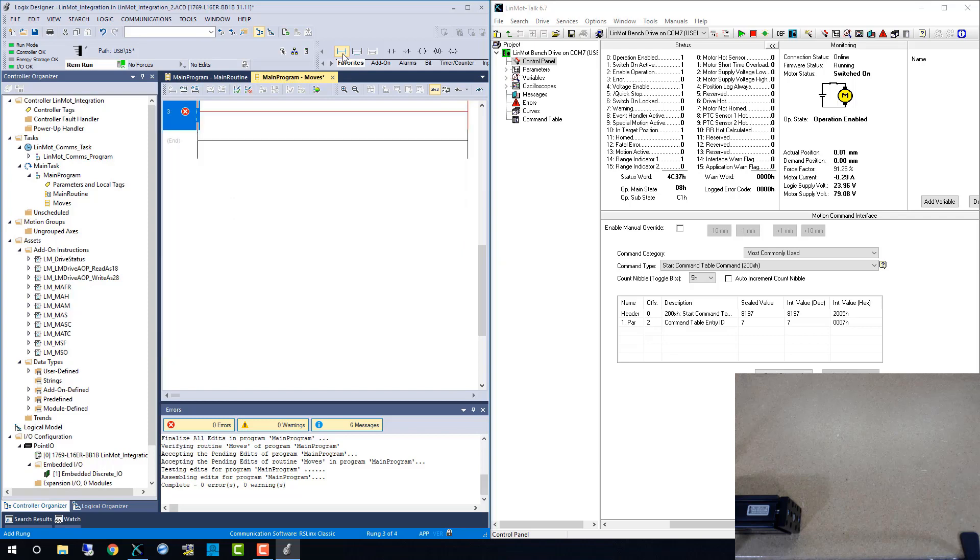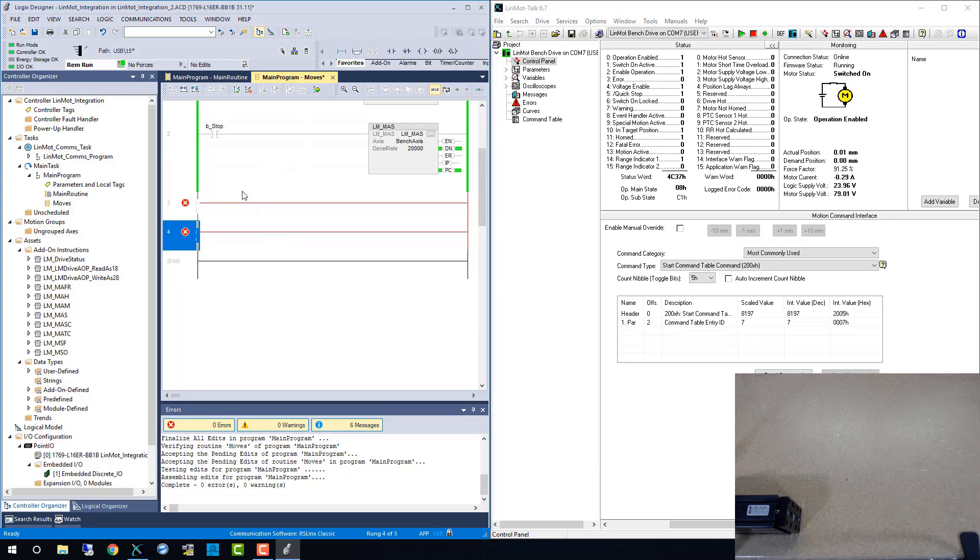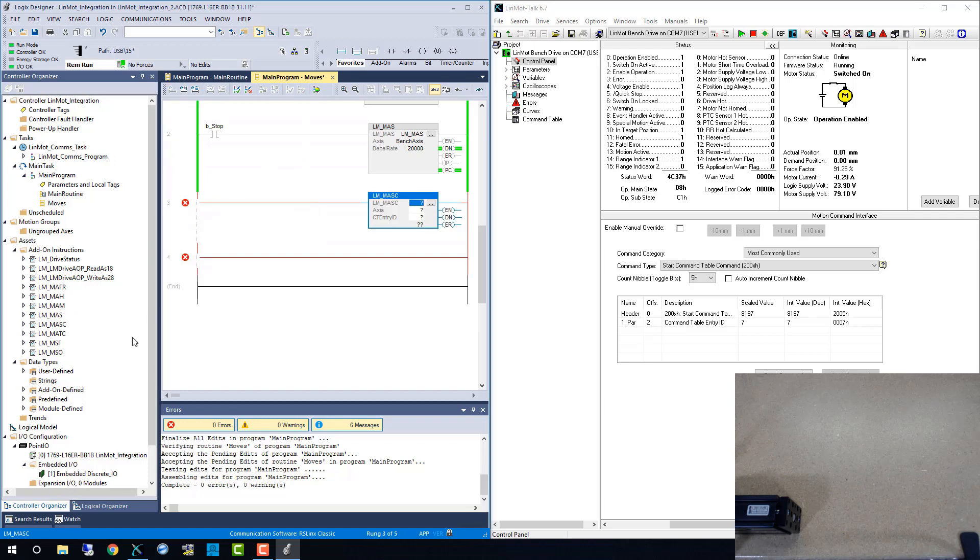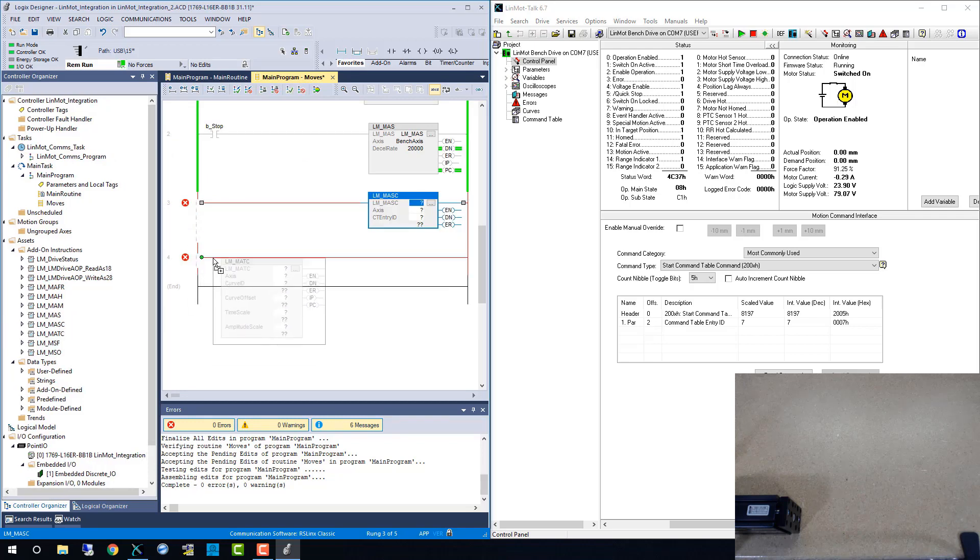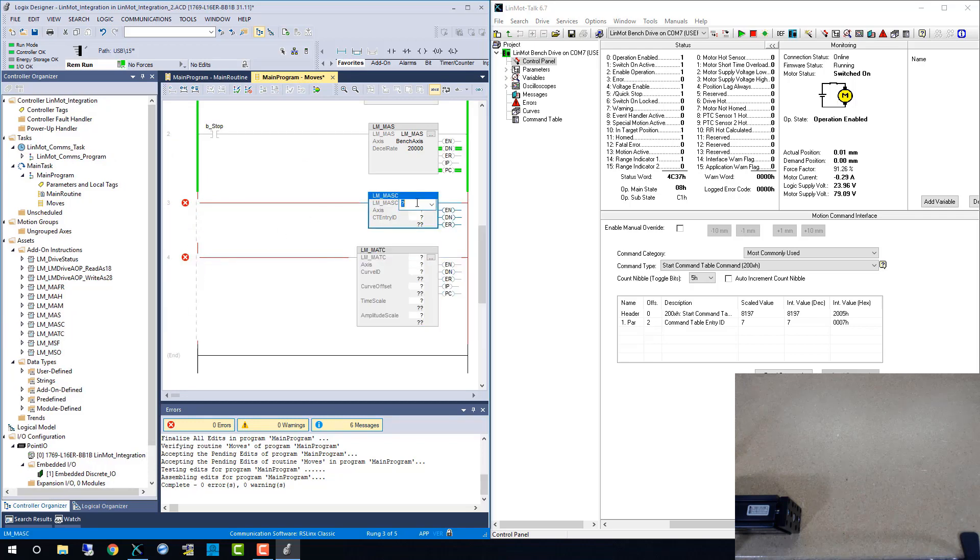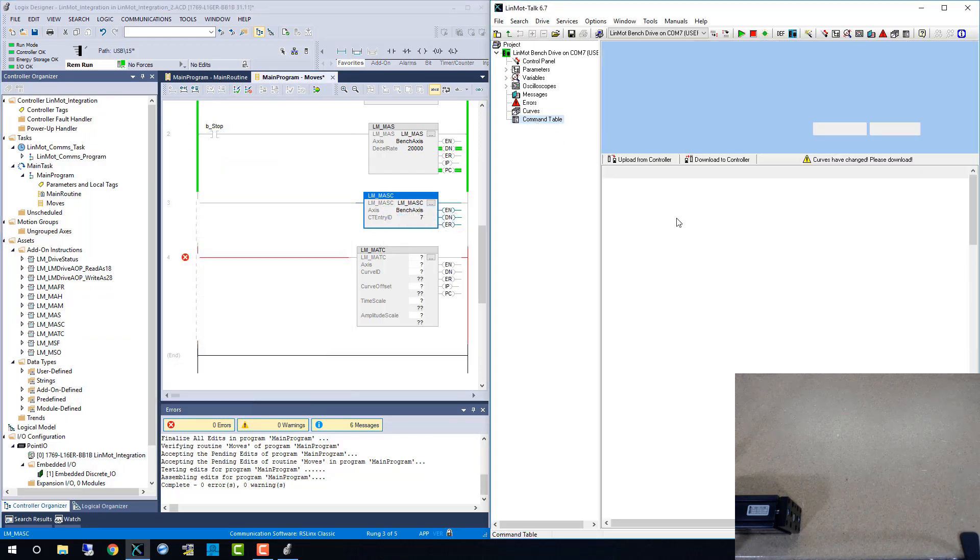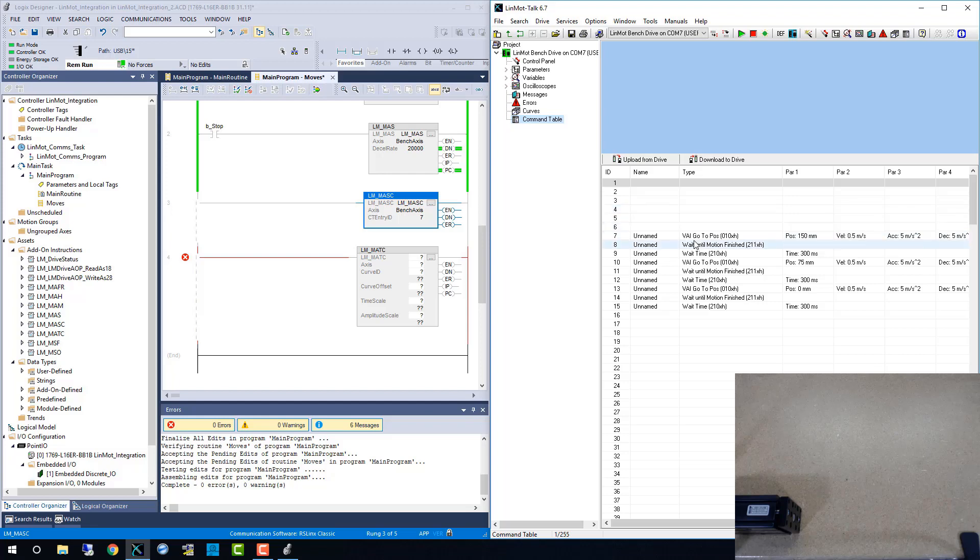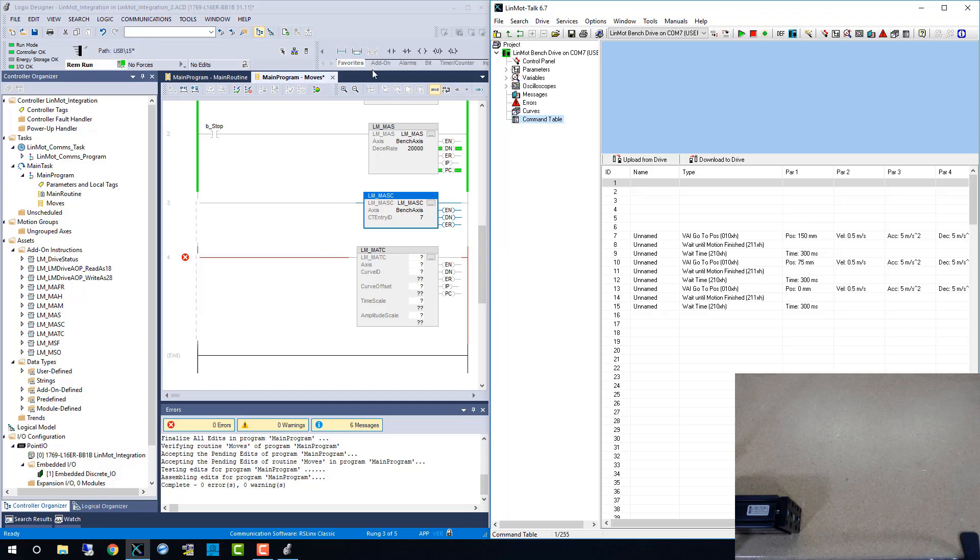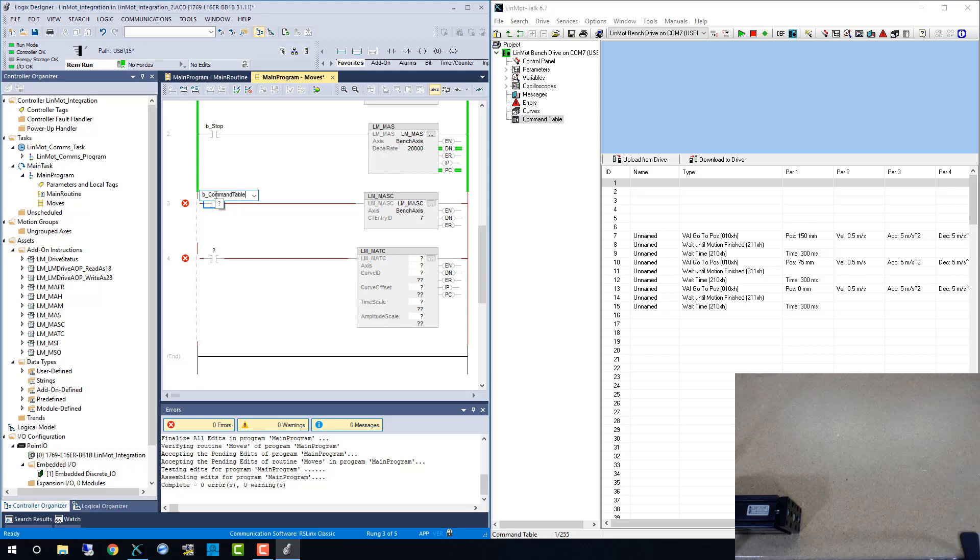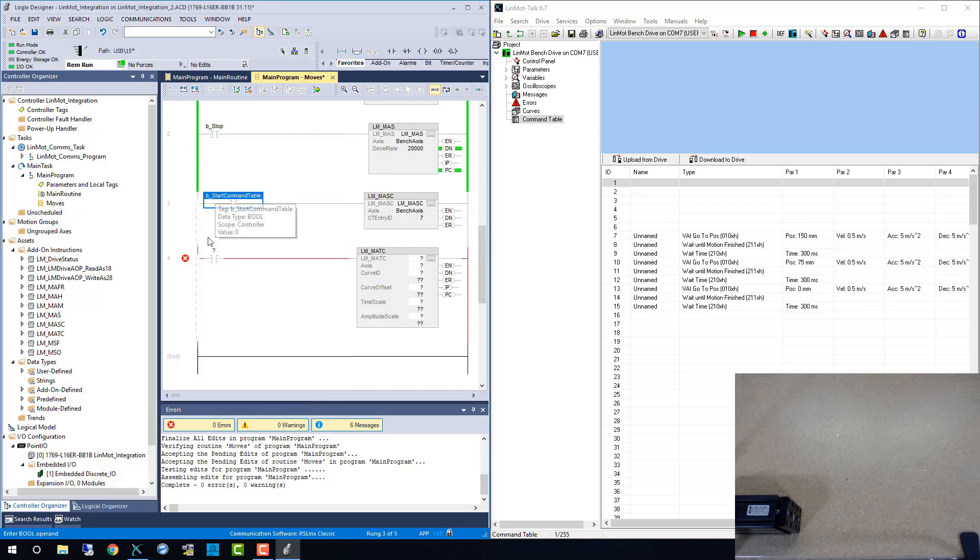Now we can add the other two AOIs we imported earlier. First up is the LMMASC, and that is the start command table command. It references the same axis and then a command table ID. The command table is stored within the LinMot drive. Here we are starting on line 7 and going through a basic movement sequence to 150mm, 75mm, and then 0mm with a dwell between each move.